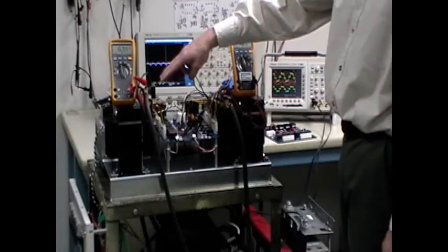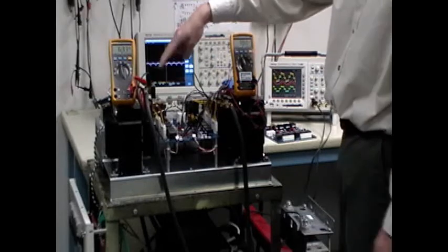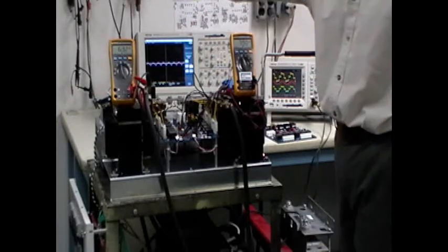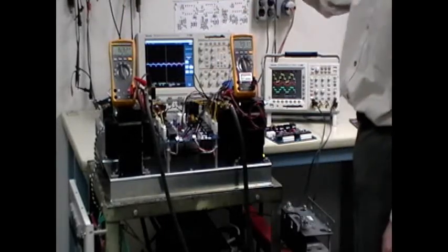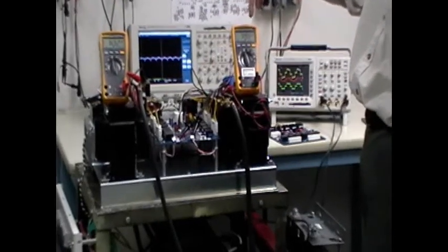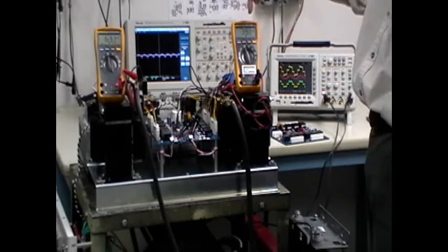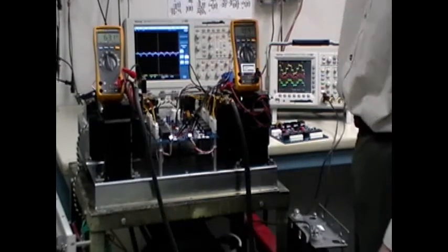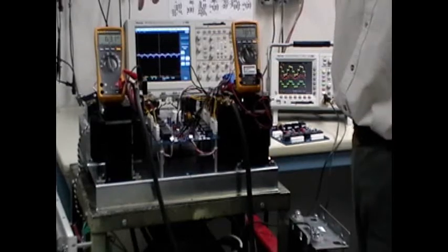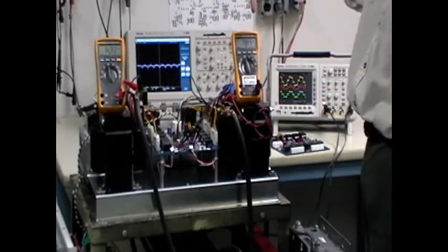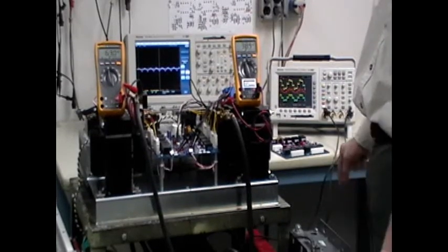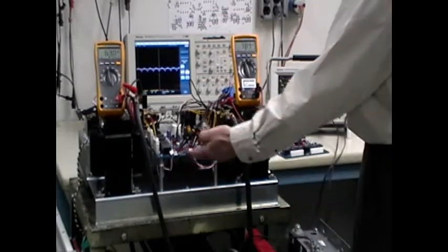We have the 50 millivolt 100 amp shunts here. So the scaling is 50 millivolts is 100 amps. On the meter, we have 63.2 millivolts, which is about 126 amps. And here we have 39 millivolts, which is 78 amps. That's about 48 amps difference out of 200. So we're talking about a 24 percent mismatch in current without any feedback.